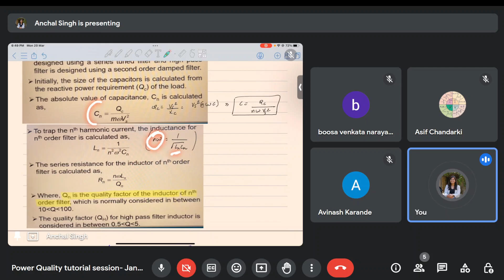Then we know that the resonance frequency or the system frequency is given by omega equals 1 by under root LC for an LC filter, right? So if I want to tune this filter in order to compensate for the nth harmonic current, then n omega will be equal to 1 by root LC. So I'll just put n omega here, and I have already found Cn. So based on this equation, I can find the value of Ln. And using the quality factor, in order to find the attenuation, what kind of sharpness I want, based on that decision, I'll be able to find the value of the resistance R.